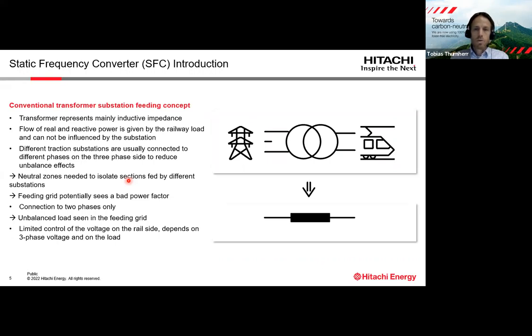Also important to say is that different traction substations are usually connected to different phases on the 3-phase side. The reason for that is that with this setup, the unbalanced effects can be reduced. Because of that, neutral zones are needed to isolate sections fed by different substations, because otherwise the power flow between these substations cannot be controlled. So this means that each catenary section that is fed by a different transformer is isolated from the other sections.